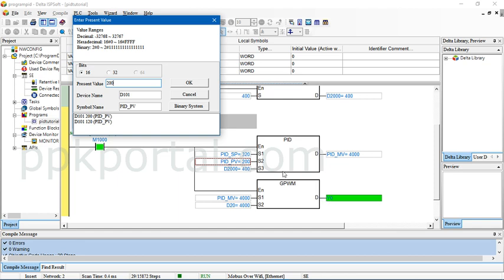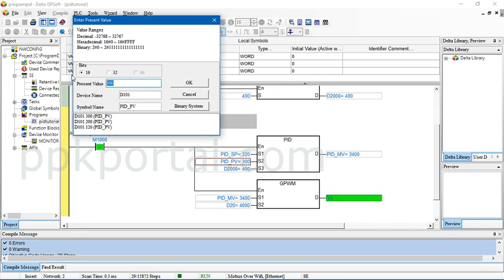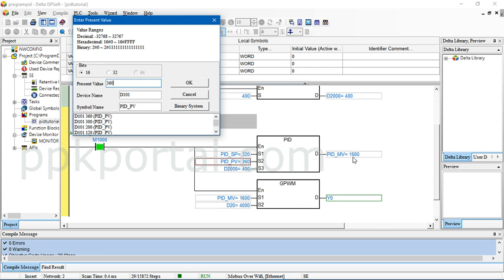See, the value is coming down and see the output is becoming intermittent pulses. It did not reach the temperature because I am still holding it, so again the PID automatically went for full opening. I will increase the temperature again to 300. See the value is again decreasing but it is waiting. Now the output is off. Let me try to cross the value like I will put 360. This feedback is more than the set point and the output is reducing. The scan sampling time which I gave is a little large. You can reduce if you want to get more responsive behavior.